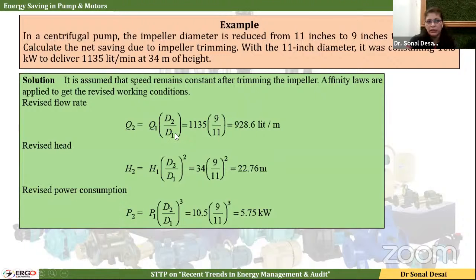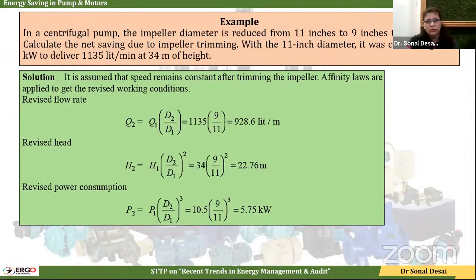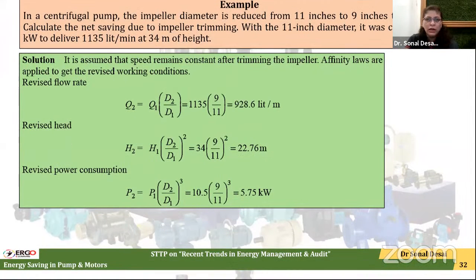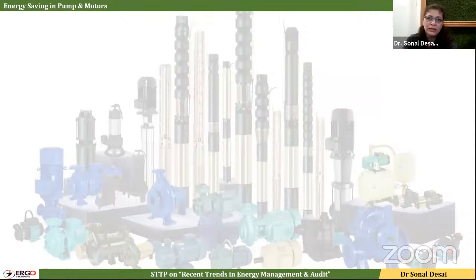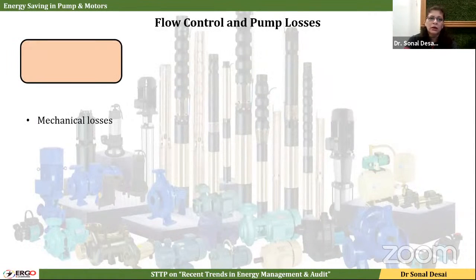Initial flow was 1135 liters per minute, as mentioned. We can see that flow is reduced from this to 928 liters per minute. Likewise, head is reduced from 34 meters to 22.76 meters. And the power consumption, you can see, has reduced to almost half, 5.75 compared to 10.5. So friends, what is the cost involved in impeller trimming? It's almost nothing. With a few $100 of trimming cost, we can save energy in the impeller.